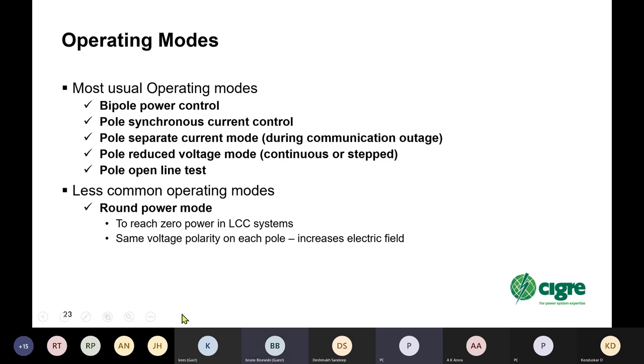That can mean that you have a non-dispatched power offset in a system, which can be troublesome if the contracts are not friendly to that kind of restriction. When operating in round power mode, you have the same voltage polarity in each pole. It increases the electric field. And also it's sometimes difficult to decide when you should use round power and when you shouldn't. So it's something that you can consider, but not often used.